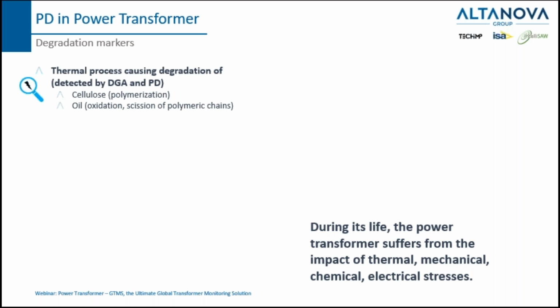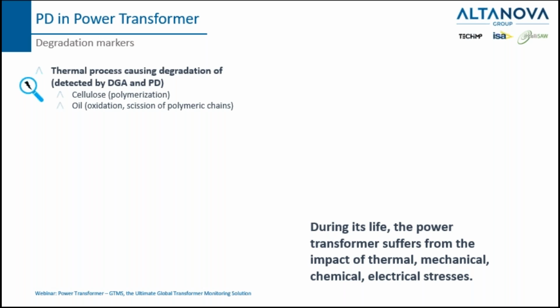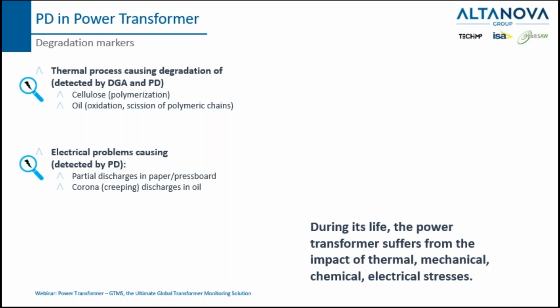In particular, as you can see here, thermal processes can cause degradation of the cellulose through the polymerization process, or in the oil due to oxidation or scission of polymeric chains, for example. But in this case, partial discharge can detect the degradation caused by the thermal process, and also with the DGA we can have a lot of information.